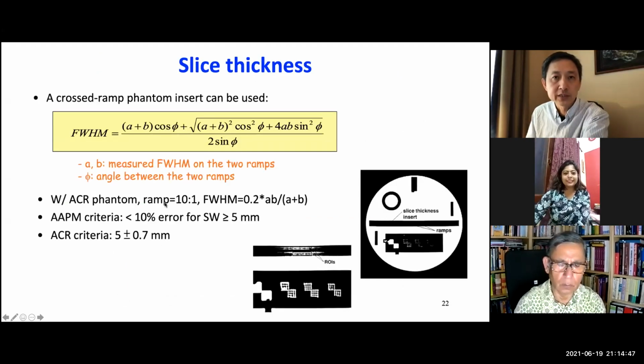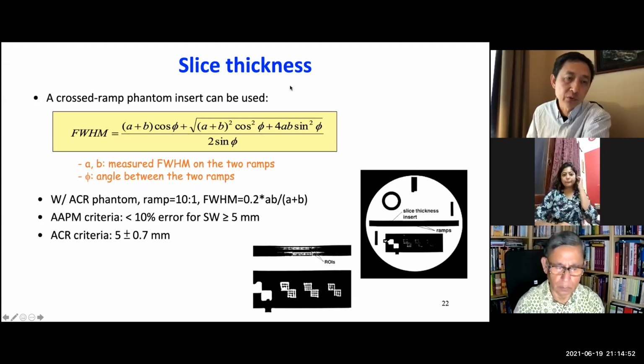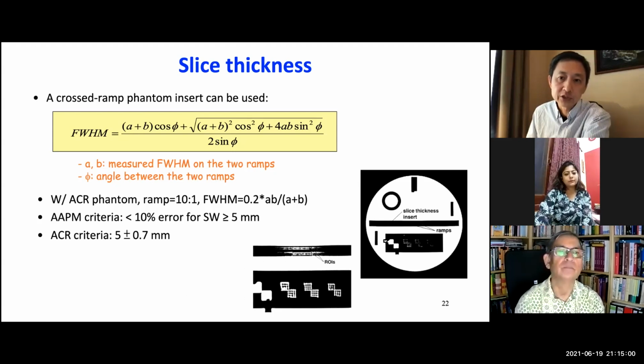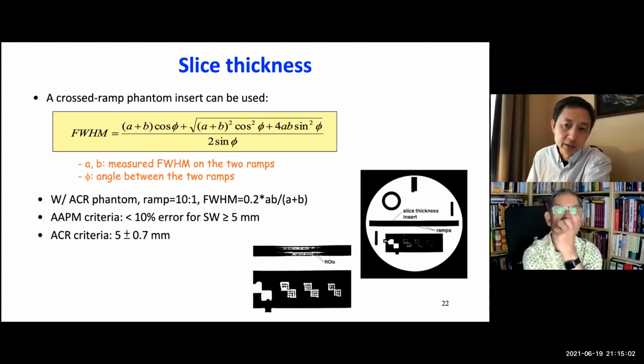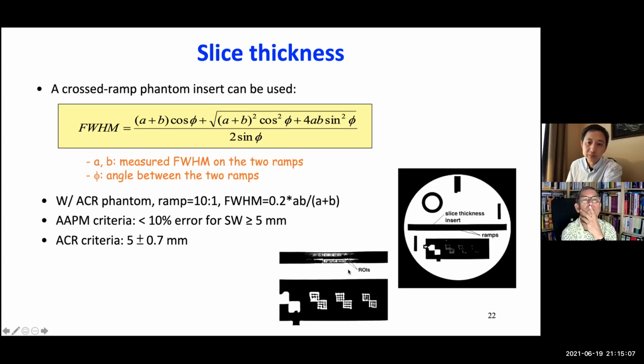The next measurement is slice thickness. In principle, we can use a cross ramp. If there's a ramp in the image, then the length of the projection of the ramp will represent the slice thickness. And when there's a cross ramp, there are 2 measurements. For example, here, those represent the image of the projection of those ramps. So the length of the ramp is representative of the slice thickness. And this is the general equation.